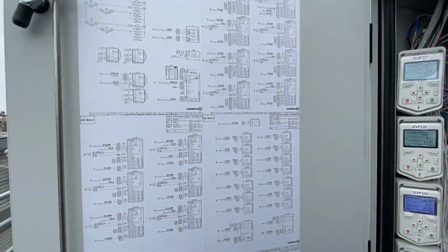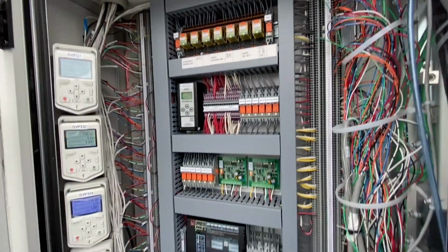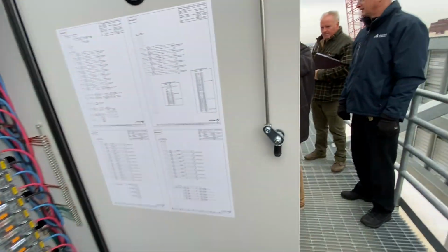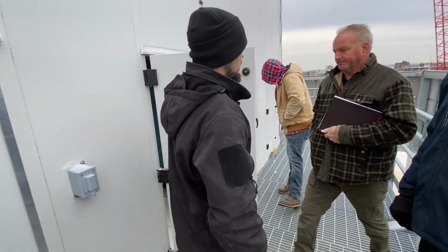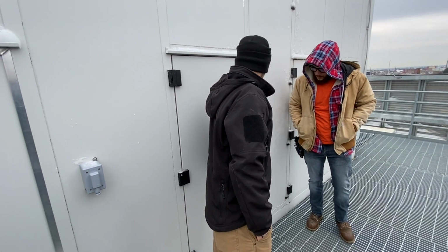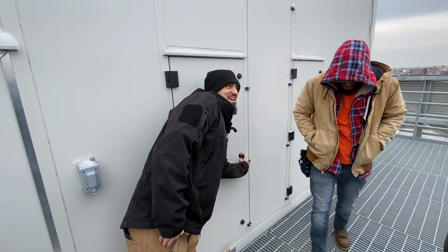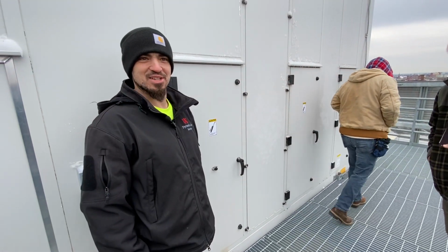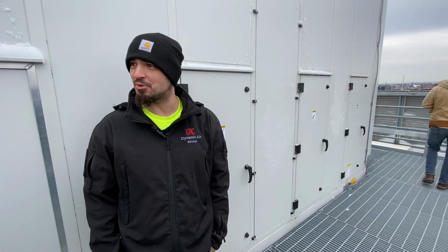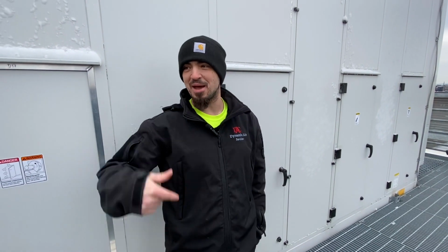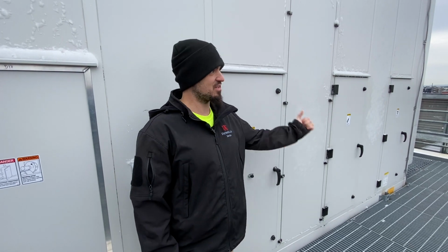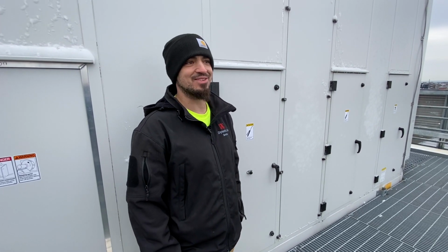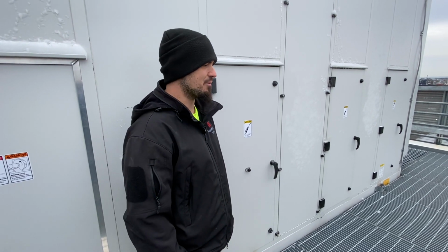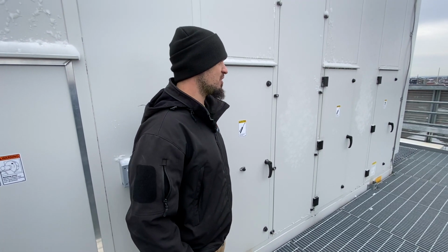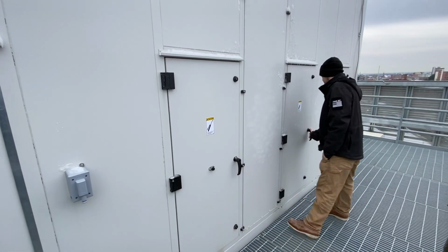So the discharge high and low are on this side right here, and then mirror image on the other side. Oh, I didn't even know that this was energy recovery. Yeah, there's an energy recovery wheel apparently. Instead of wasting the energy of the heat we're exhausting from the space, we pick that back up through the energy recovery wheel and put it back in the supply stream, so we don't have to heat as much necessarily.